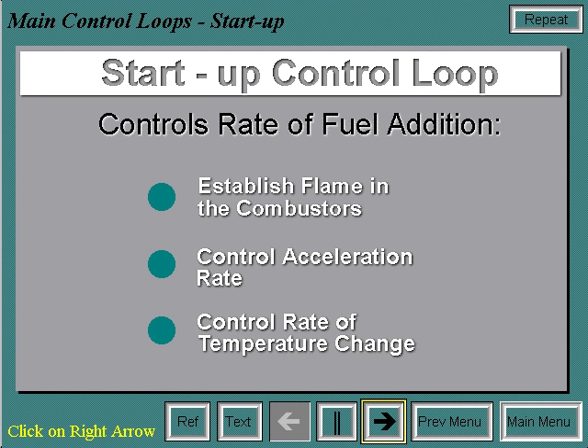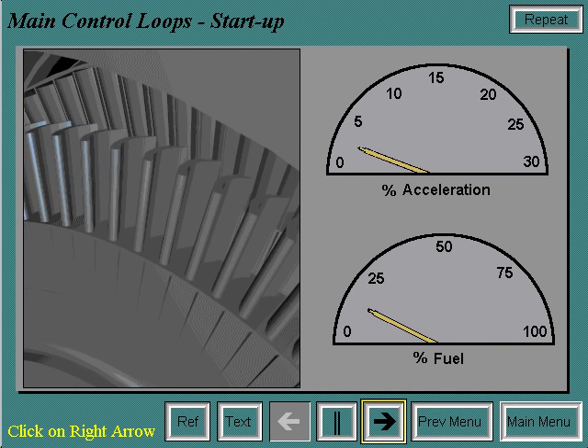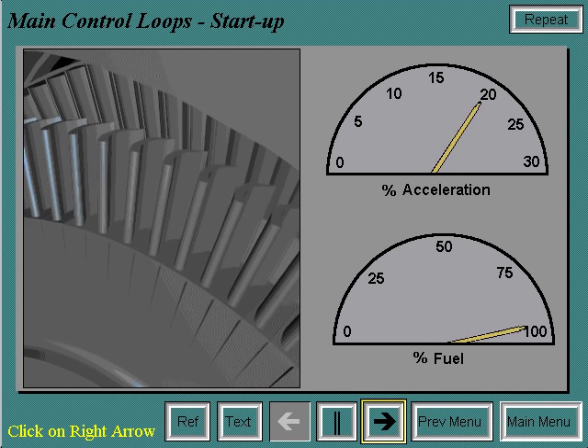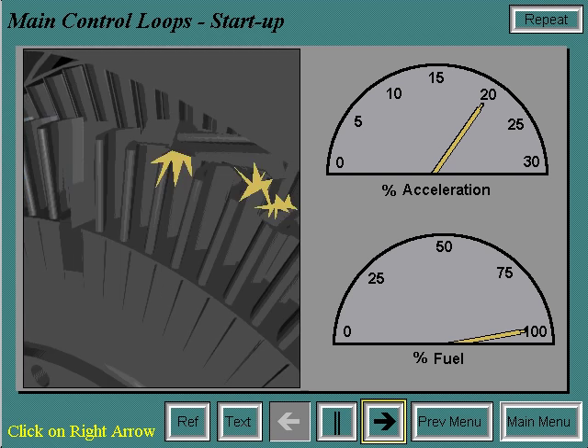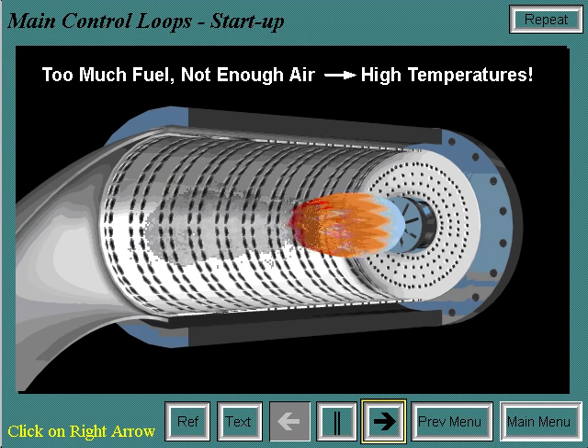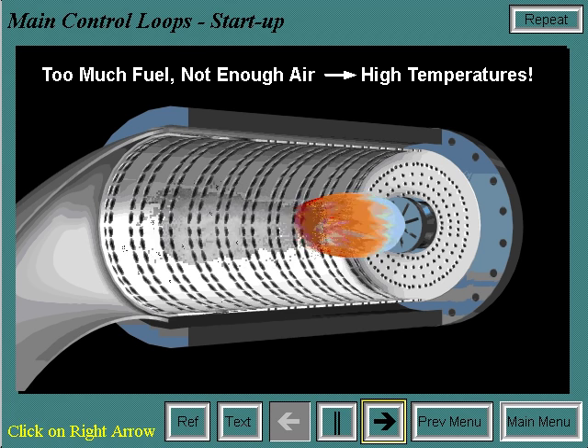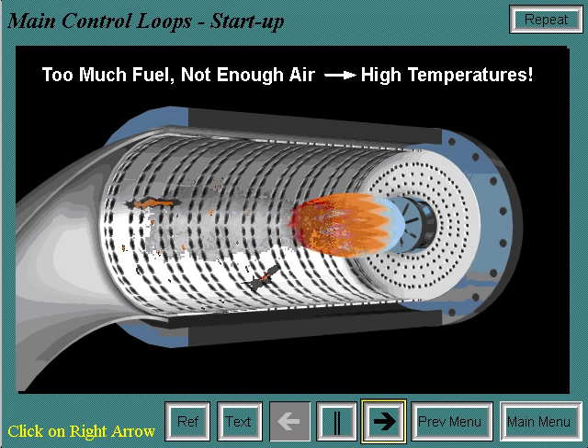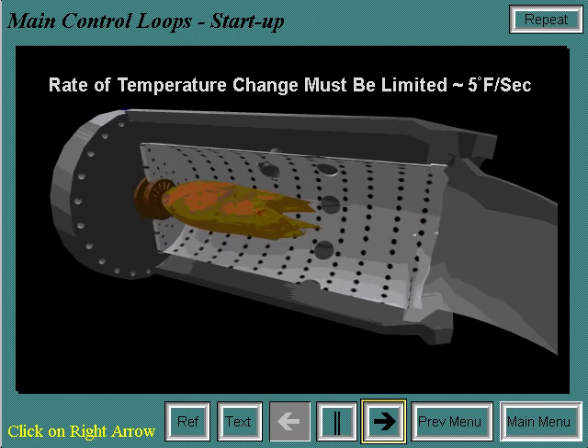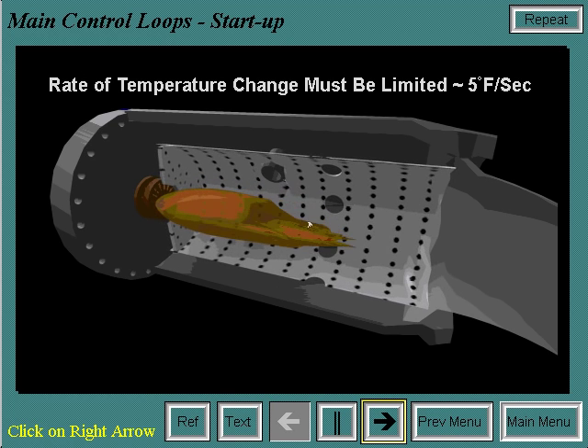The startup control loop controls the rate of fuel addition for several reasons: to establish flame in the combustors, to control the acceleration rate, and to control the rate of temperature change. Acceleration of the turbine rotor must be controlled so as not to exceed the allowable forces on the rotor, as exceeding the limit can cause heavy damage. During startup, airflow rates are low; if there is too much fuel added while there isn't enough air, temperatures could get dangerously high, potentially damaging internal hardware.